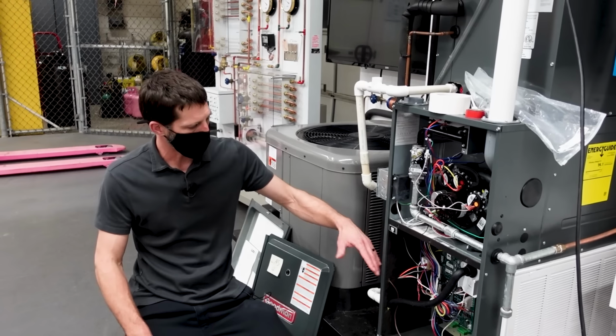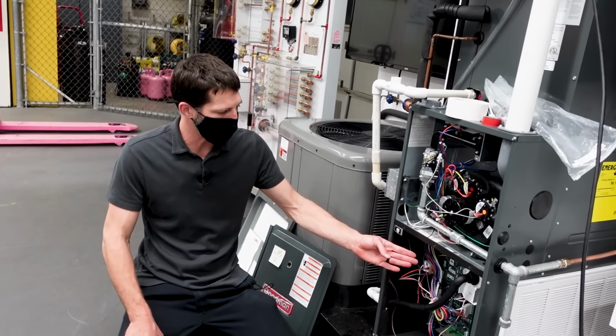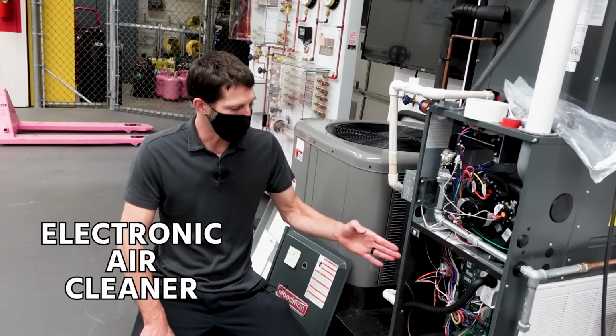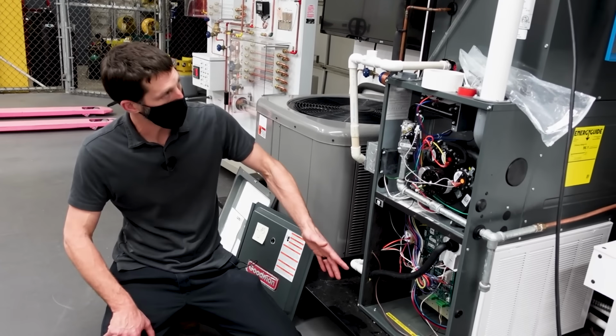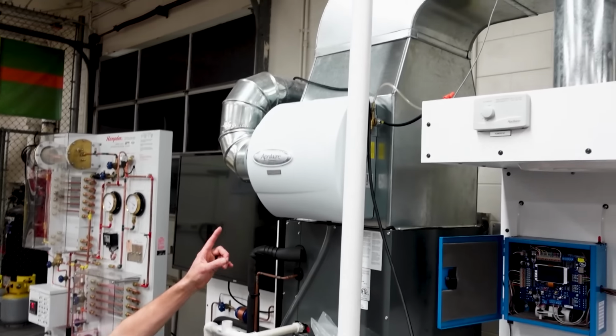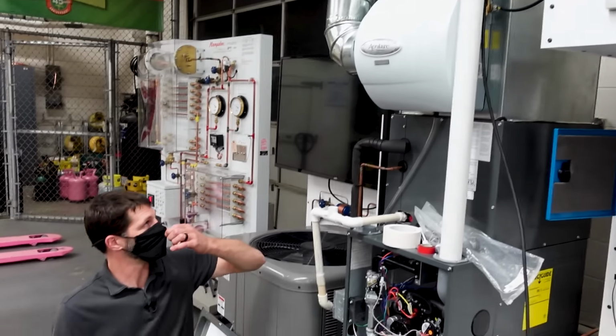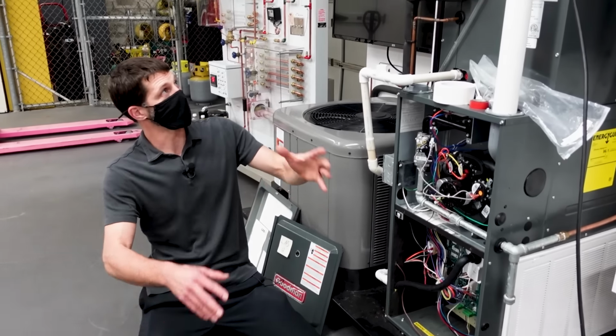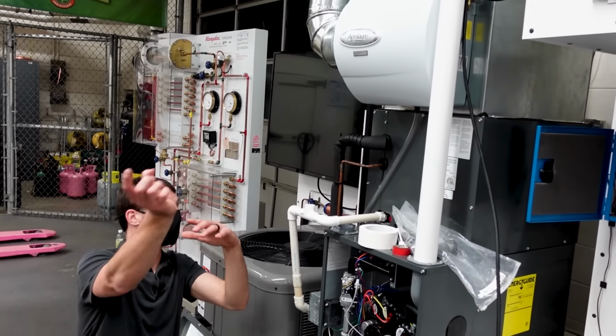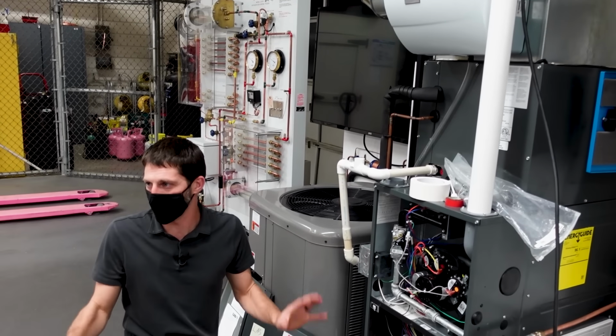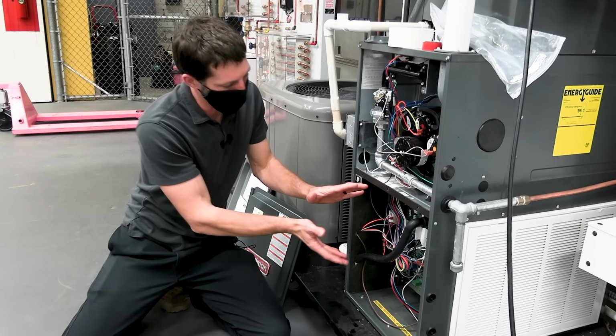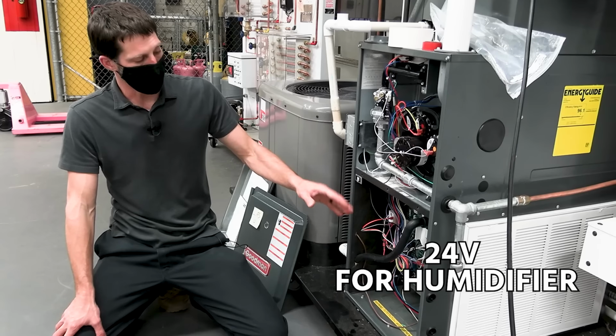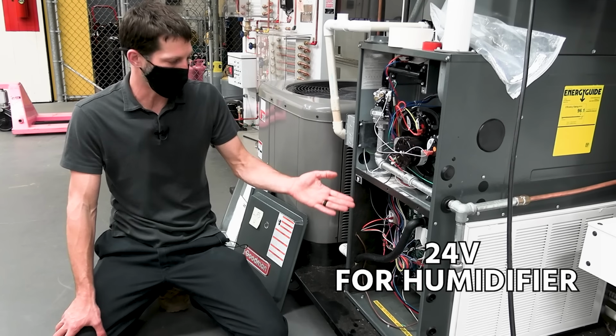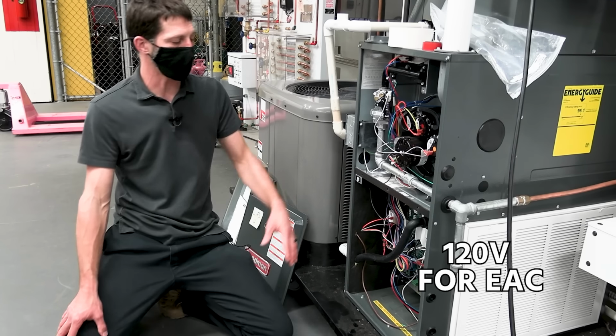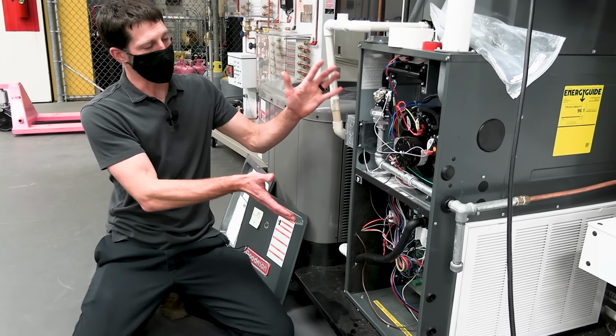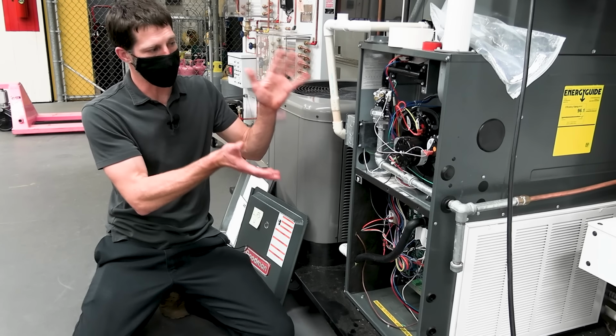IFC, so the integrated furnace control, a lot of times you have a tab there for the EAC, which is the electronic air cleaner, and also the humidifier. In this case, you have a bypass humidifier, which are preferable. I've seen other humidifiers that are actually taking air from the attic and pushing it into the duct, like all kinds of nonsense, you know, it's crazy. But anyway, the newer integrated furnace control boards have a 24 volt for the humidifier and a 120 volt for the EAC. These indoor gas furnaces are typically single phase 120 volt.